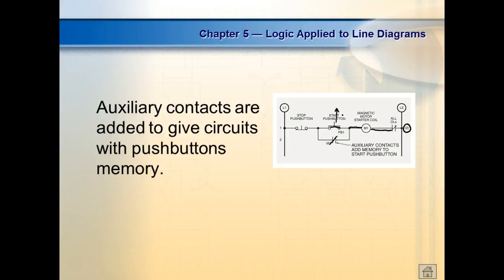But the normal way we do it is just do what? Push the stop button. As soon as I push the stop button, we lose our current path. The relay drops out. This contact right here opens and it sits there. And so this is called a seal-in circuit. It's also called a what?